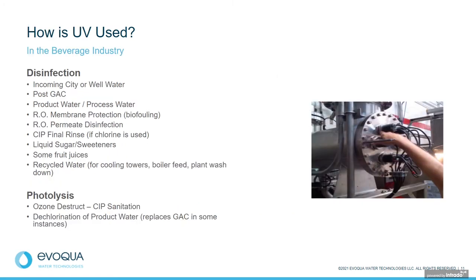So what are the applications? For the beverage industry, it can be multiple applications and uses in the plant depending on your process. So incoming city water or well water can be used, depending on the quality of the incoming water. Post granular activated carbon. This is the most common use of UV in a beverage plant because when you take the city water, remove the chlorine with the activated carbon, you then have unprotected water, and carbon towers can breed bacteria. So UV is often used, and that's most often.